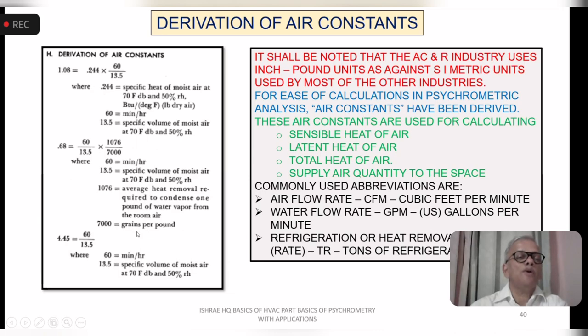And this is the grains per pound. So 7,000 is the grains per pound. To simplify this, it is like the unit when you are talking about the distance between, say, Pune and Mumbai, you talk in kilometers. But when you are talking about room dimensions, we talk in meters. They are all equal. When I say meters, I can always convert it to kilometers or vice versa. In the same way, the grain is a smaller unit, used when you are dealing with smaller numbers, otherwise you will end up with 0.004 or 0.006, and then there are possibilities of error in the calculations. To minimize that possibility, we use the smaller unit. This is 7,000 grains per pound. If it is the SI system, you will use 1,000 grams per kilogram.